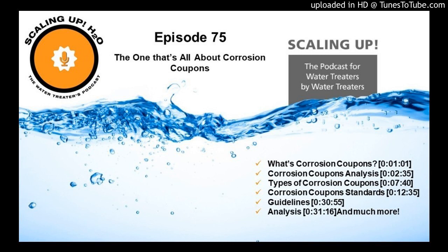I'm going to go into one of the items on the acceptable, non-acceptable list, those standards that I was talking about. So let's talk about mild steel in an evaporative water type system. Anything less than 1 mil per year is considered excellent. Anything that's less than 3 but greater than 1 would be considered very good. And that goes all the way up to anything that's greater than 10 mils per year being unacceptable. And there's a good range, a fair range, and a poor range in between that. So a lot of times I will weigh a corrosion coupon, and let's say it will come back as good. And that would be 3.1 mils per year.